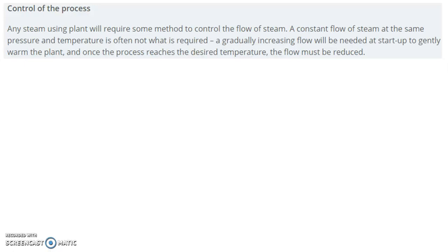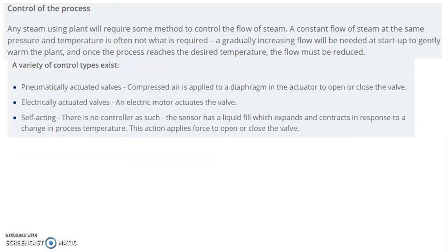Next is control of the process. Any steam-using plant will require some method to control the flow of steam. A constant flow of steam at the same pressure and temperature is often not what is required. A gradually increasing flow will be needed at start-up to gently warm the plant, and once the process reaches the desired temperature, the flow must be reduced. A variety of control types exist: pneumatically actuated valves, electrically actuated valves, and self-acting valves.